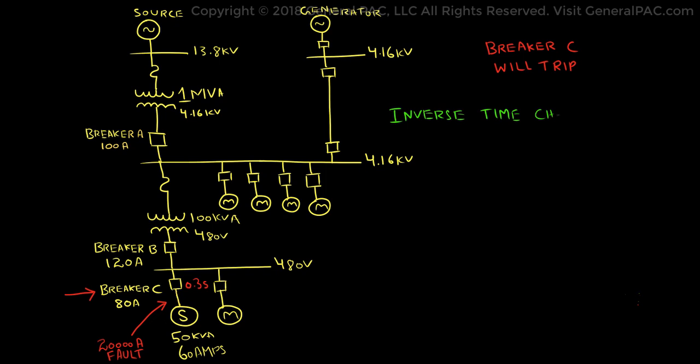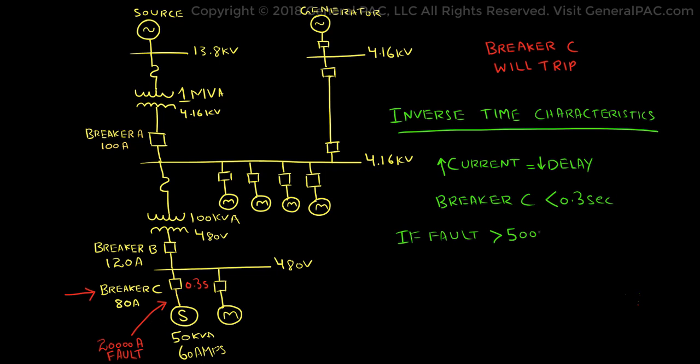If we compare this with the inverse time characteristics, a higher current level would mean a lower time delay. In the case of breaker C, the delay time would be much less than 0.30 seconds. Depending on the inverse time characteristic curve of the breaker, it might trip after 0.10 seconds of delay. Conversely however, if the fault current was only 5000 amps, then the delay time would be much greater than 0.30 seconds.